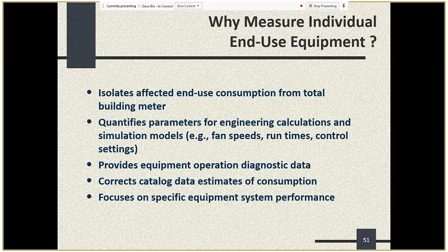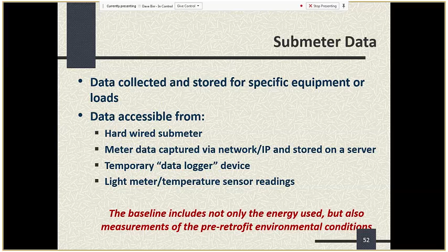So, if you do get sub-meter data, which in this case is primarily the PV system, there are a couple of possibilities. You can have a hardwired sub-meter, or you could have meter data via a network and an IP stored on a server, or you could even have a temporary data logger device, as you would, for example, on a lighting occupancy sensor. But baseline includes not only the energy, and I'm sort of repeating myself here, but also the measurements of all the pre-retrofit environmental conditions associated with that energy consumption. That's important to remember because nothing stands in isolation. Everything's connected to everything else.